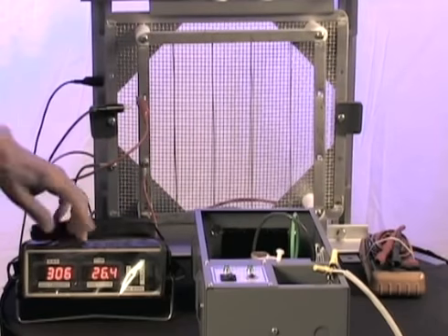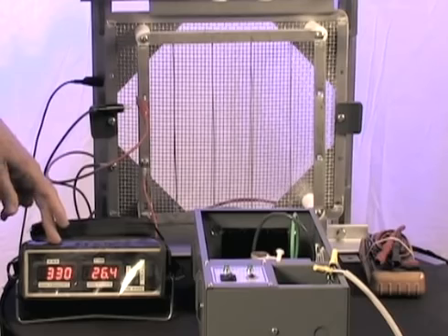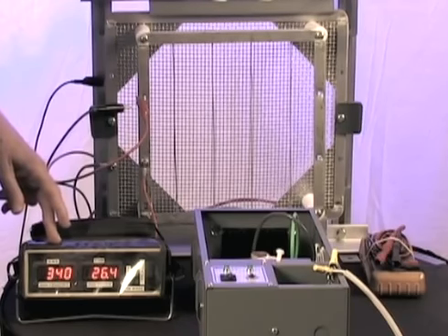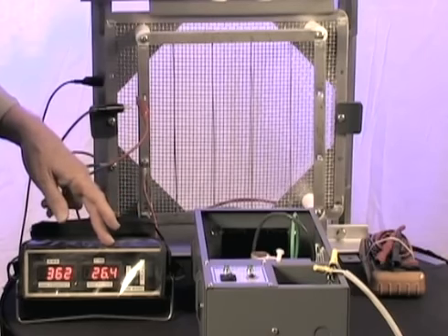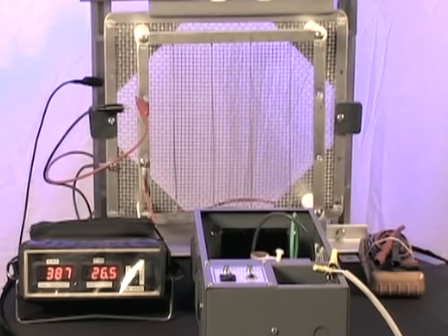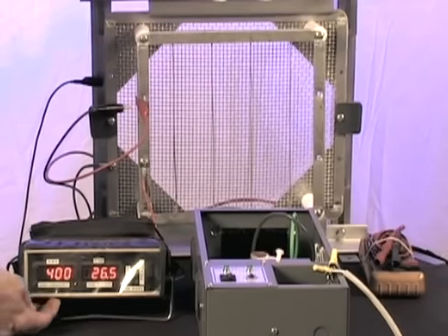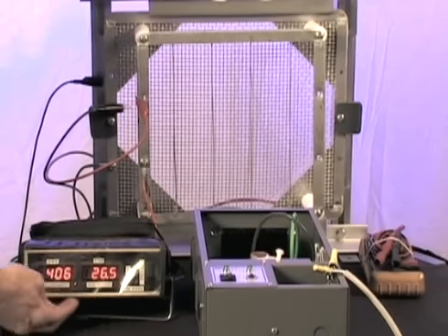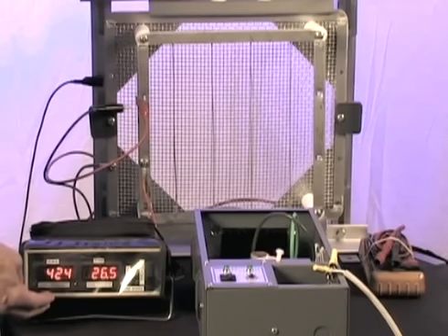Look at your test kit, and if the readings are between 3 and 500 for your high frequency, you're at the proper value range. If the high voltage is between 22 and 29,000, you're within the operating range of it also. With our CosaTron system on, monitoring it from our test kit, we can see that the high frequency is actually low, with the high voltage at the proper value. Restoration of the high frequency to between 500 to 800 will restore the CosaTron system to the performance values that it's supposed to be.